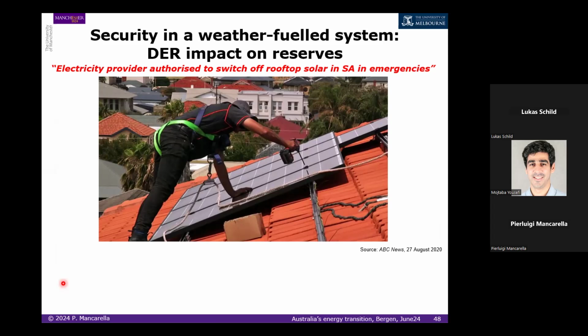This doesn't have anything to do with papers you may read about, but it's got to do with brilliant engineering. There's only one thing you can do in distribution networks at the moment to control this, which is change the voltage level of the grid. Effectively, with the transformers in the primary substations, you change the tap and raise the voltage of the grid. When the voltage becomes too high, rooftop PVs have protection mechanisms to disconnect, and they disconnect automatically.